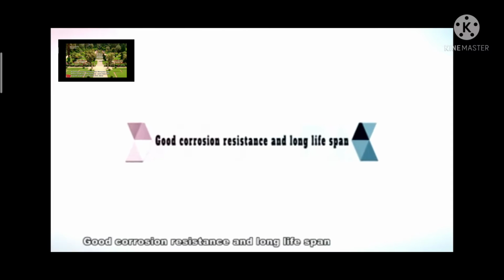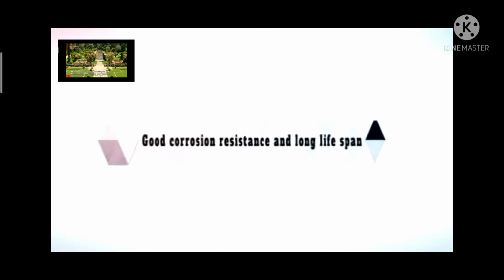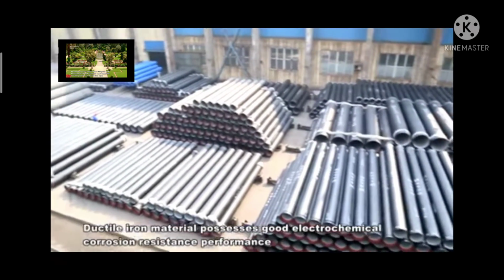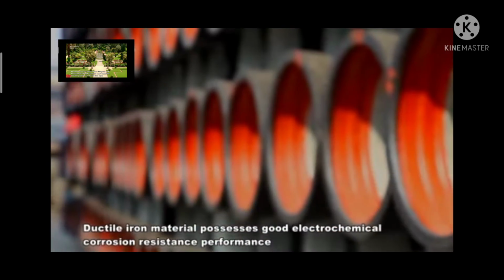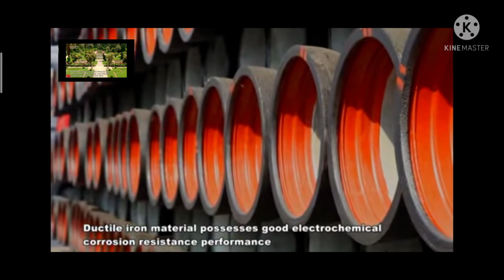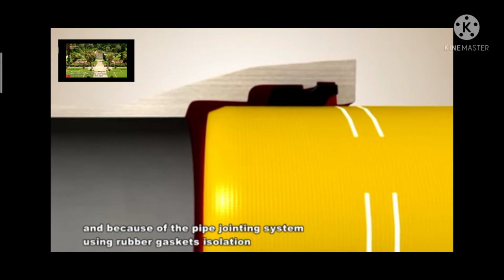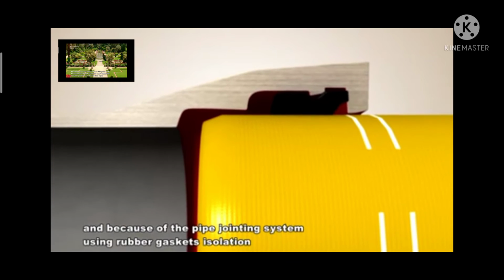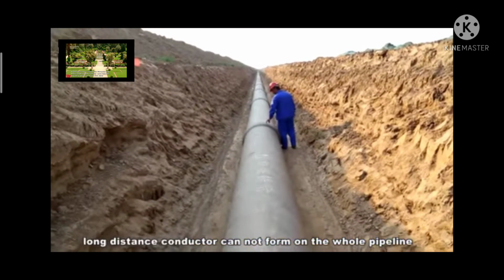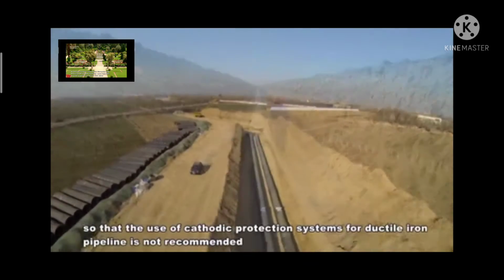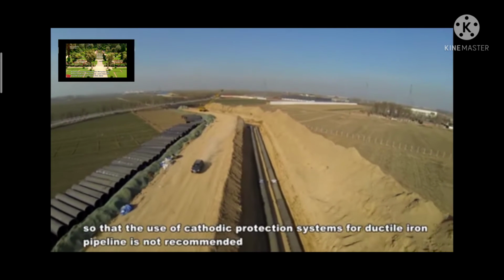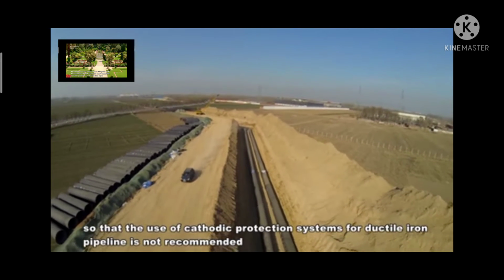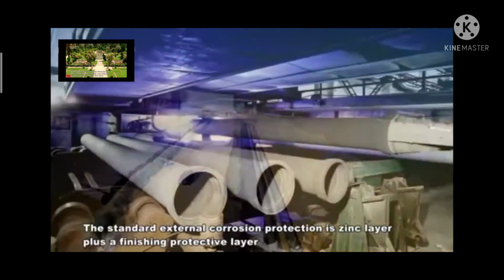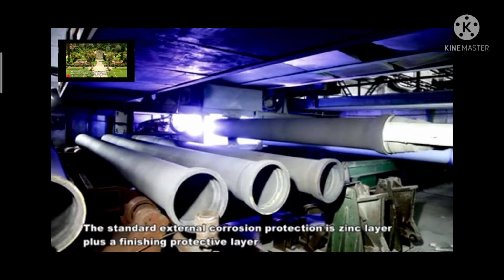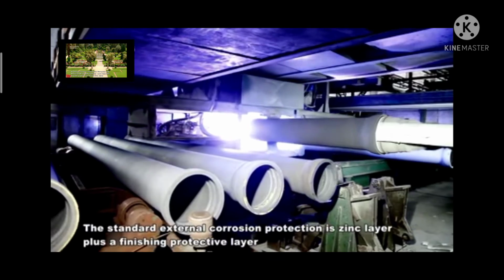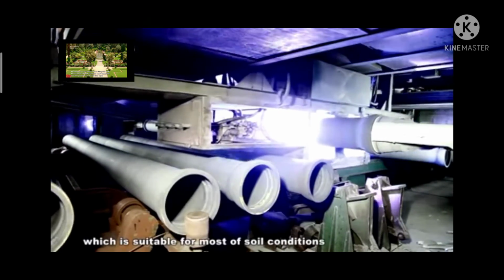Good corrosion resistance and long lifespan. Ductile iron material possesses good electrochemical corrosion resistance, and because the pipe jointing system uses rubber gasket isolation, a long-distance conductor cannot form on the whole pipeline, so the use of cathodic protection systems for ductile iron pipelines is not recommended. The standard external corrosion protection is a zinc layer plus a finishing protective layer, which is suitable for most soil conditions.